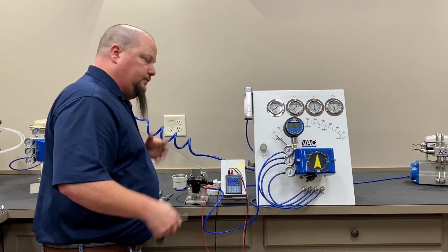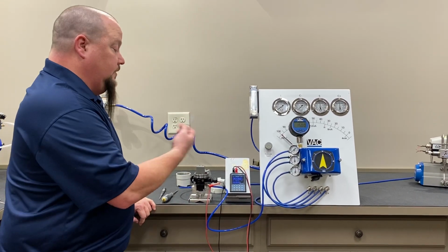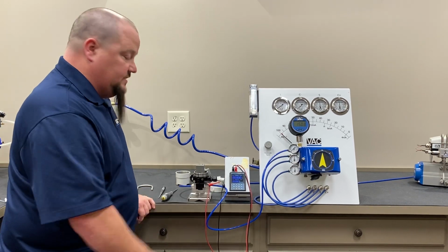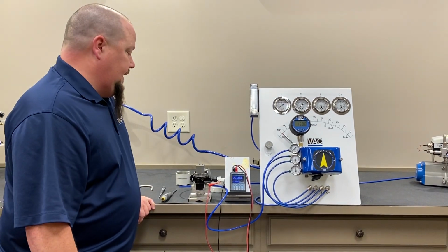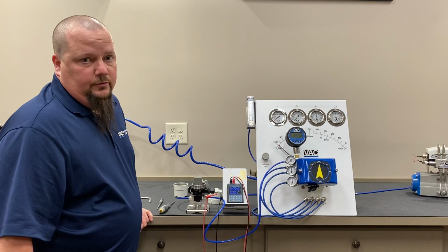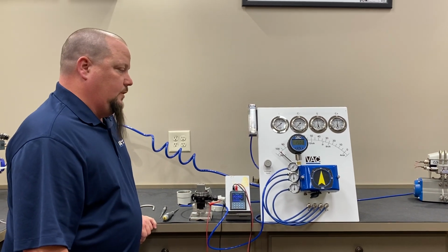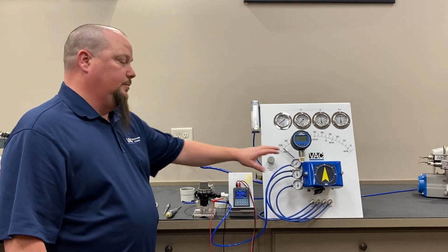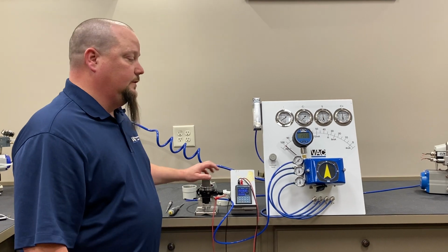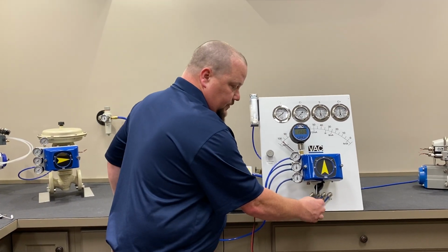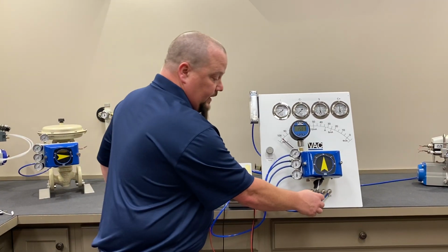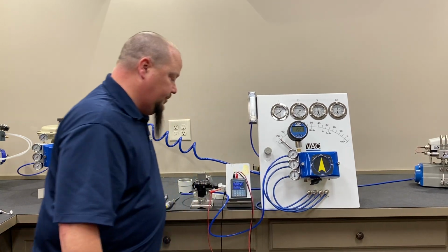Those are really only for instances where somebody has changed the settings on the IDP and you need to get it back to 3 to 15 output. Quite often people try to calibrate the positioner from the IDP, and that's incorrect. Like I said, the calibration is still done through the calibration port on the bottom of the positioner for the 0 and the span.